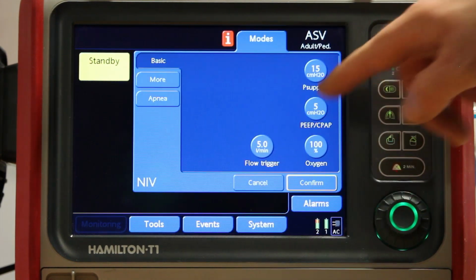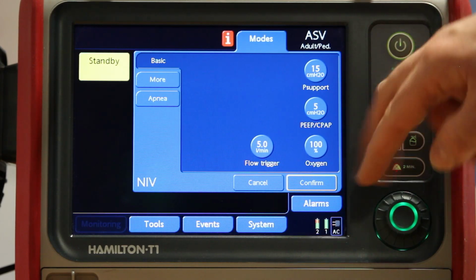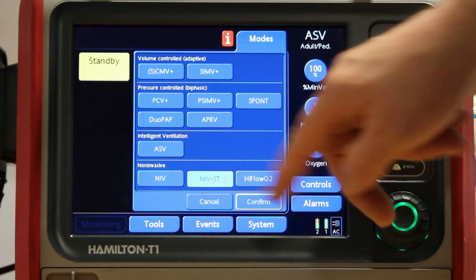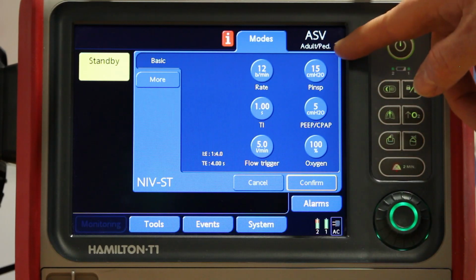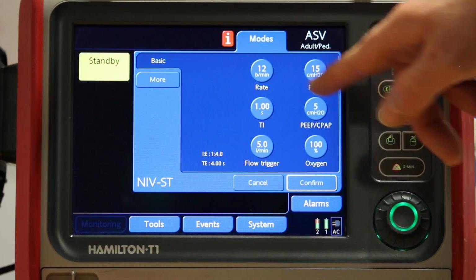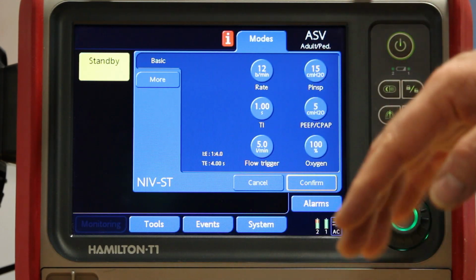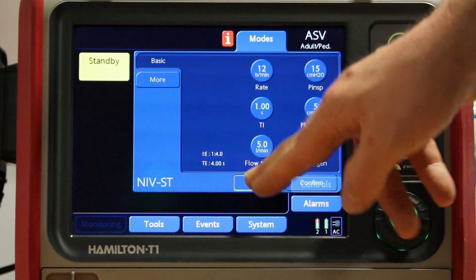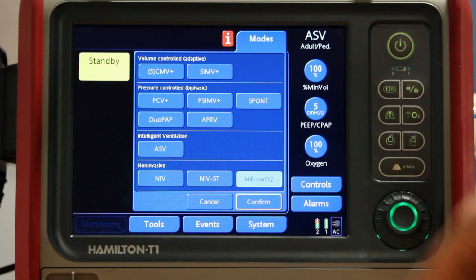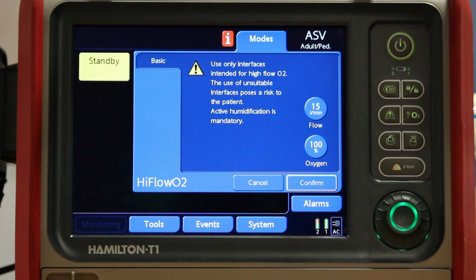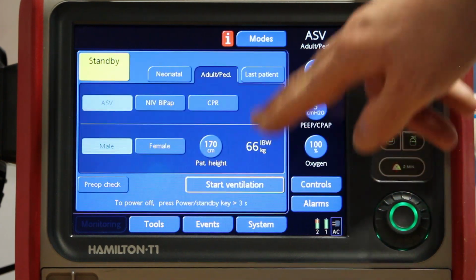NIV, which is our masked CPAP, we're just setting our support on our PEEP. And then NIV ST, ST stands for spontaneous and timed, so we're setting our inspiration pressure on our PEEP. We also have rate and an I time, so that is a bi-level non-invasive. And then we've got our high flow where we're setting our FiO2 and our flow. Hamilton will do 80 litres a minute of flow for high flow.